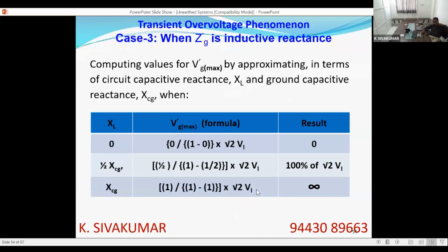Now if you see 0 means 0. If the external impedance or inductive reactance is 50% of the capacitive reactance of the leakage network, you see 100% root 2 VI is introduced. If the external impedance is 100% of the leakage capacitance, so XL equal to XC, whenever XL equal to XC, it is called a resonance. So you can see the voltage is almost infinity. It is not practically infinity, because the network also contains some resistance. So the resistance to an extent reduces it, but it is very high.